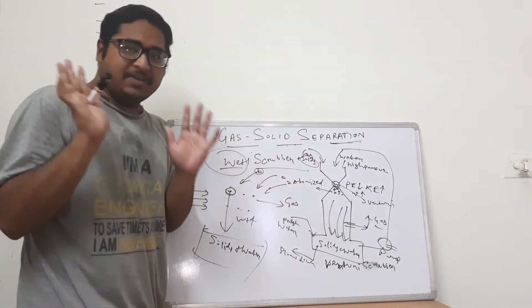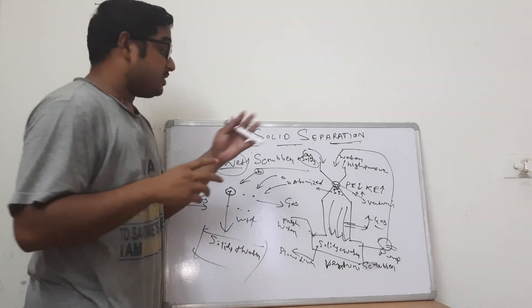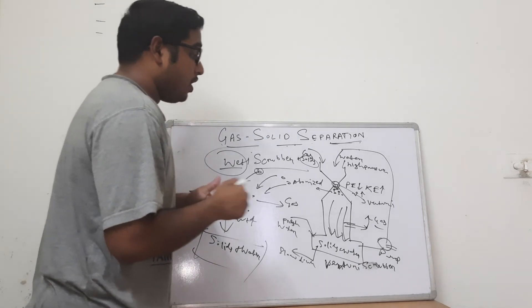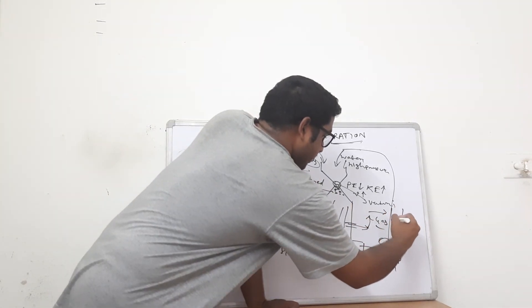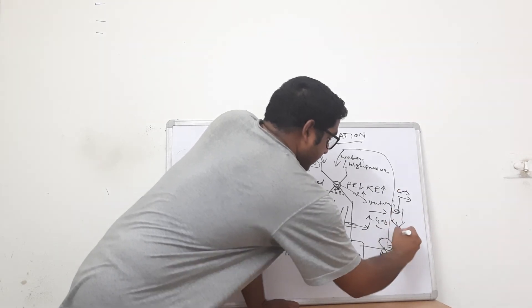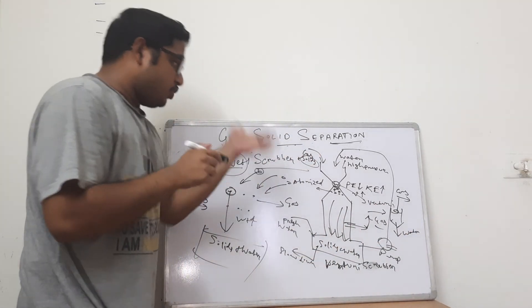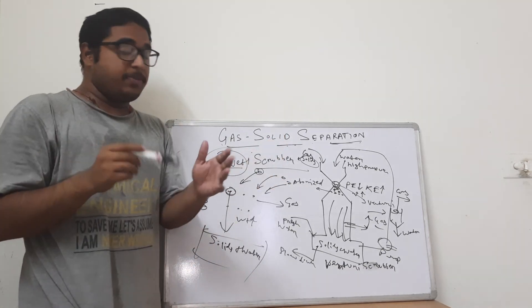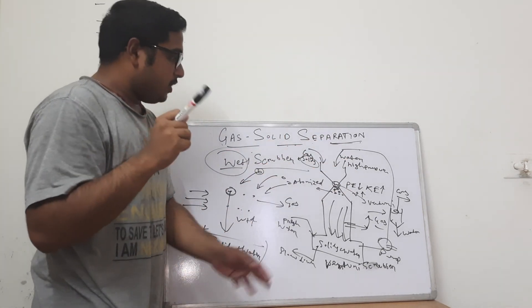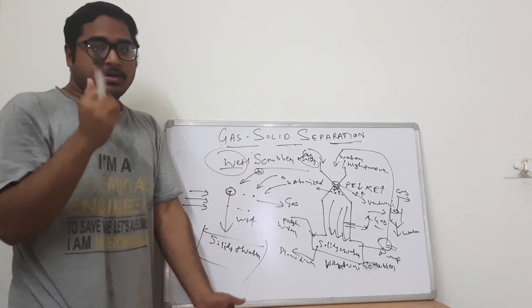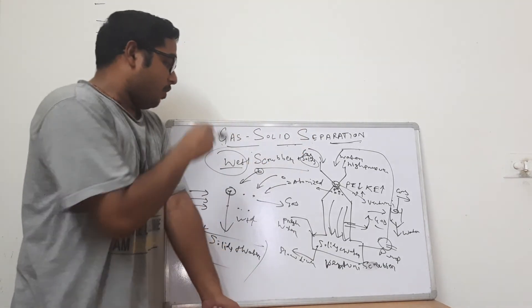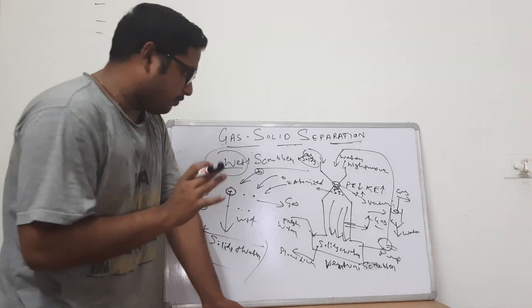You have removed the solids effectively, but there might be a carryover of liquid droplets along with the gas. That is why the venturi scrubber is generally followed by a cyclone separator, which rotates the flow in a circulatory motion, allows the gas to escape, and deposits the water droplets. So the venturi scrubber or wet scrubbing system is generally followed by a cyclone separator to ensure the gas is free of water droplets. First we remove the solids, then we remove any entrained water droplets in the cyclone separator.